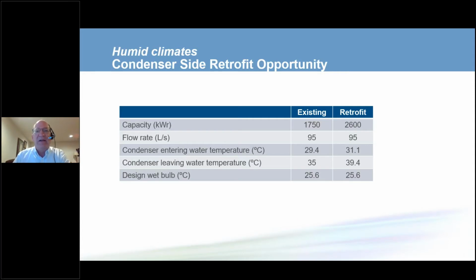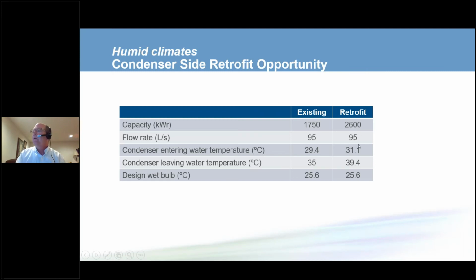By selecting the new chiller at the proper conditions, we can easily increase the heat rejection and therefore the cooling capacity provided by that chiller by 50%. Because we can use the same outside air, we can use the same flow rate, the same design wet bulb temperature, and by having that higher delta T, we can use the same cooling tower.